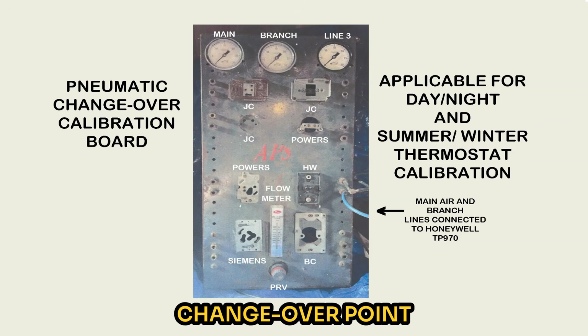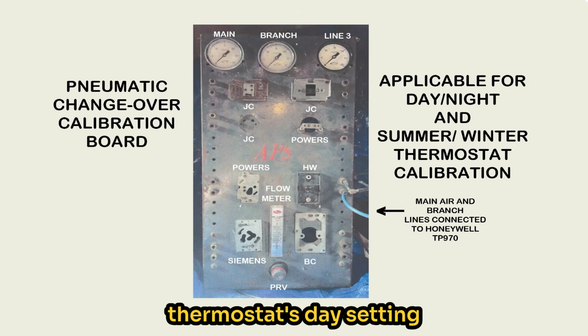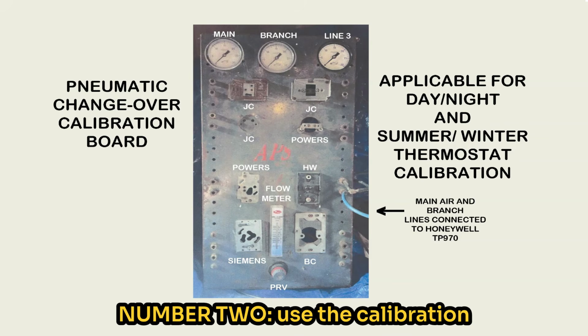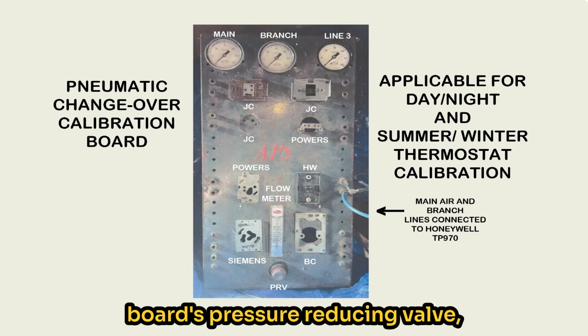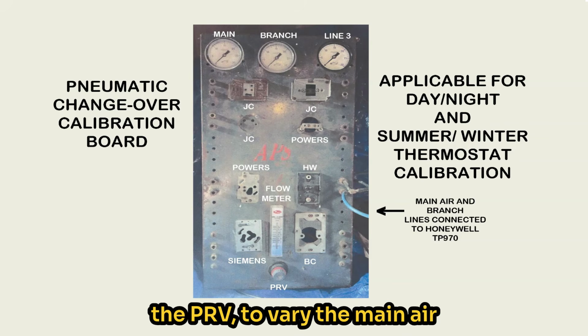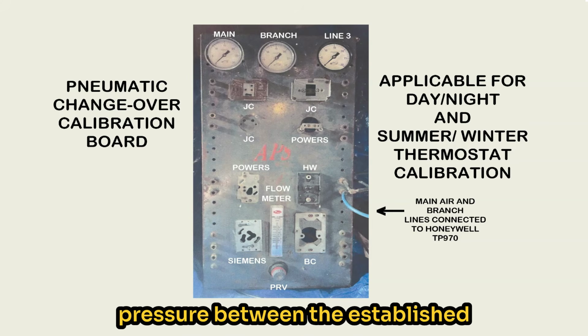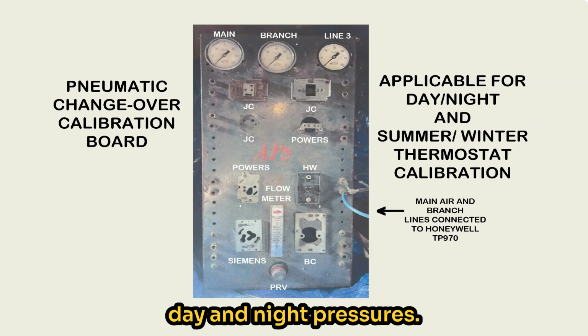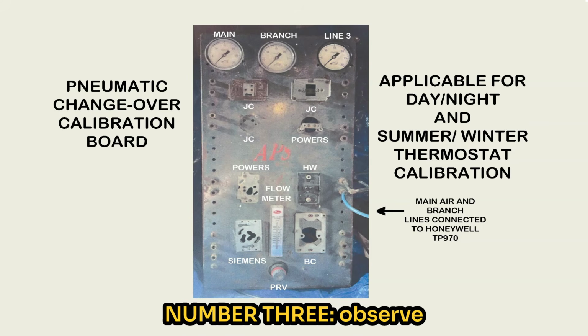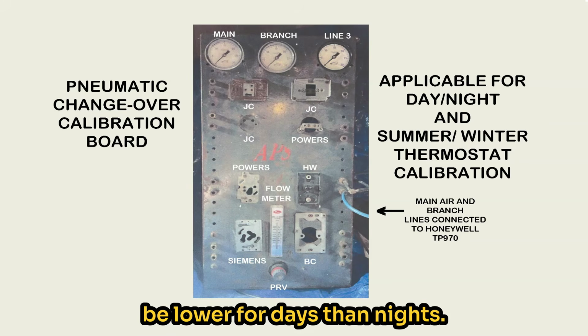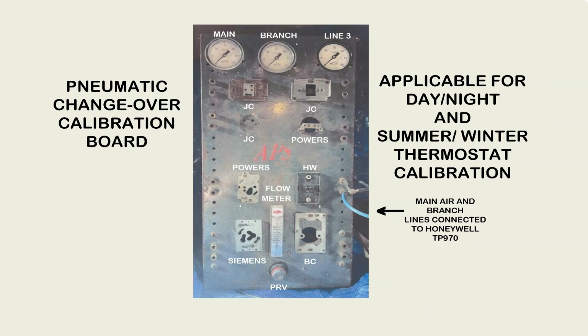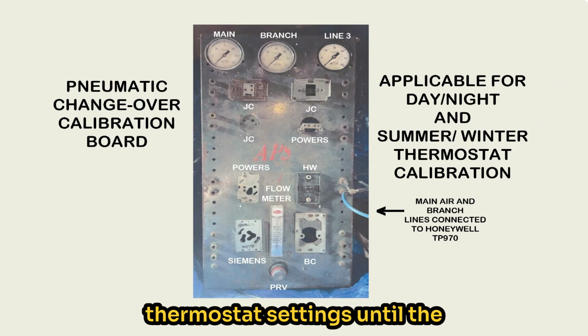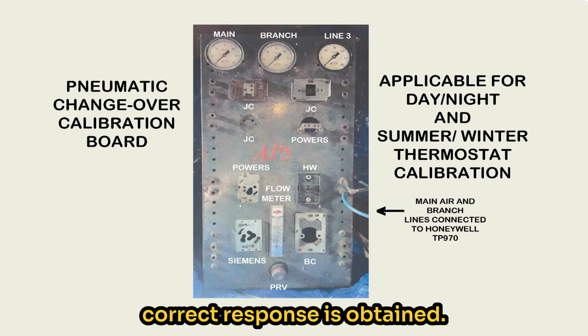Adjusting the changeover point. Number 1. Adjust the thermostat's day setting to a temperature above the room temperature. Number 2. Use the calibration board's pressure-reducing valve, the PRV, to vary the main air pressure between the established day and night pressures. Number 3. Observe the branch pressure. The branch pressure for a direct-acting thermostat should be lower for day than night. If it is not, adjust the thermostat settings until the correct response is obtained.